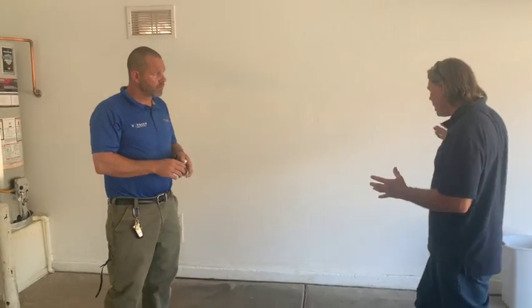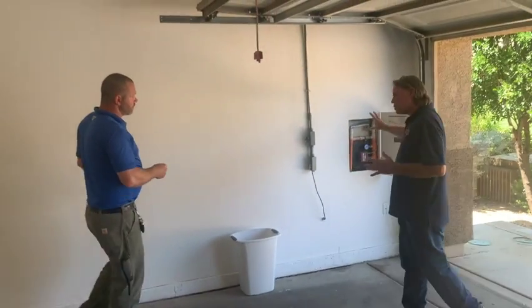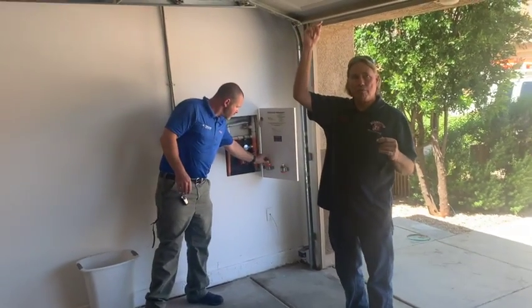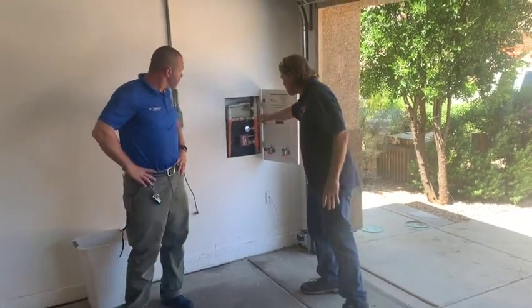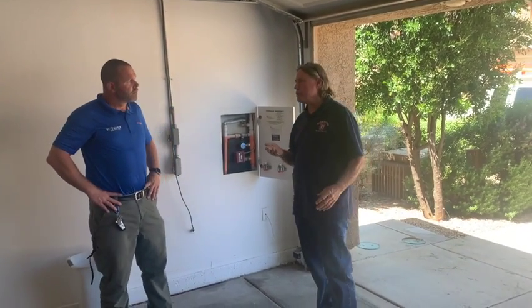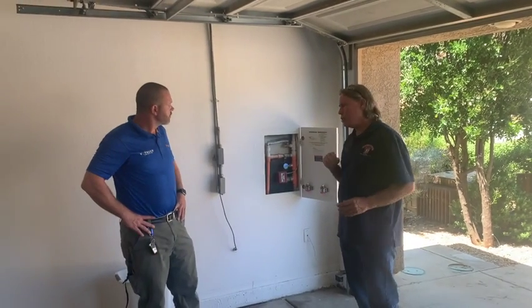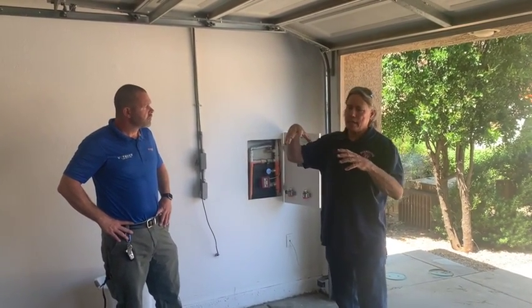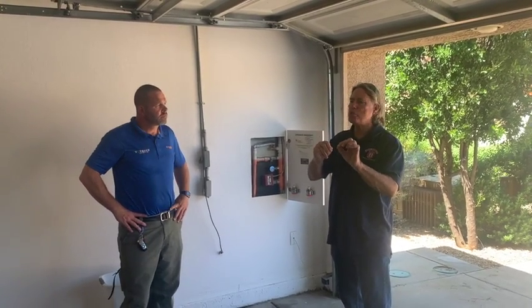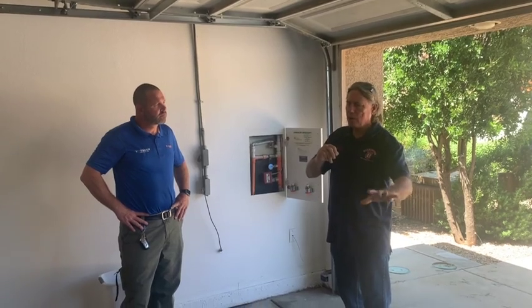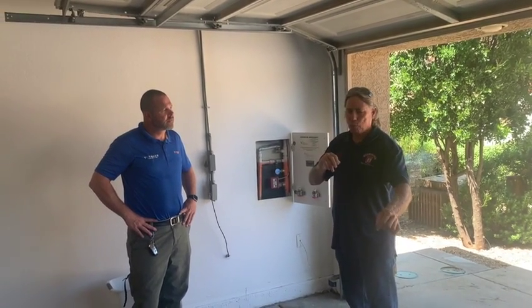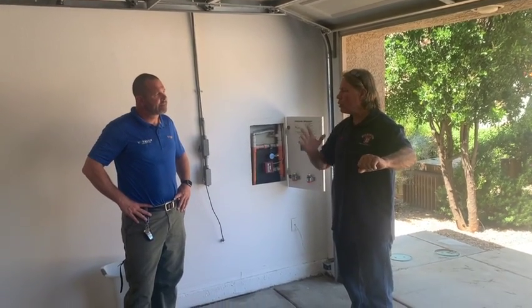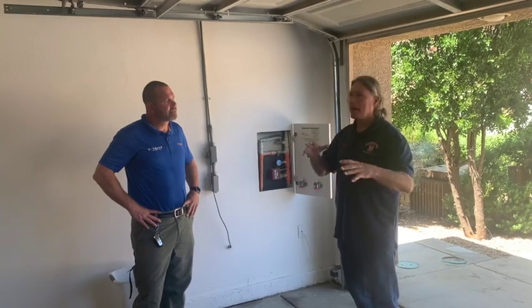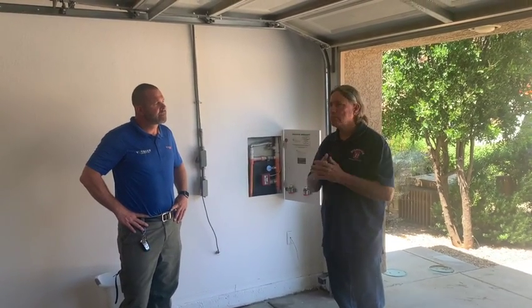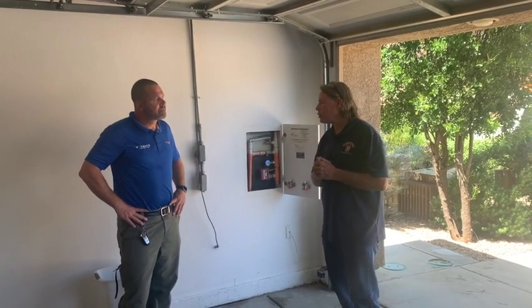Absolutely. So now we can show you the maintenance aspect. Once we pipe a system, this is where it starts, and this is the control. Now it runs a main piping throughout the home. This particular one is CPVC. There are different materials that are used in different types of systems, but this one's a very common one to be used. So once we've piped all the heads and the sprinklers are in the right place, in the very most demanding area, we bring a pipe out and a valve, and we call that the inspector's test. So now we have the water piped outside the house, so we can actually flow the system, maintain it, and test it without having water in the home, without damaging or worrying about touching any of the sprinkler heads themselves.